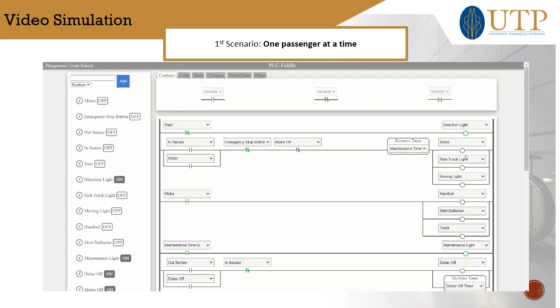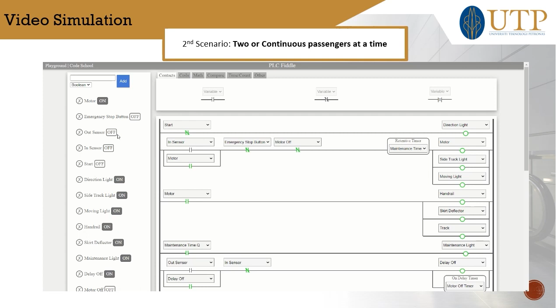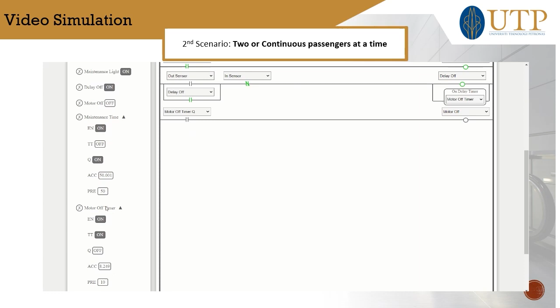Alright, so let's move to the second scenario, when there are two or continuous passengers. The in sensor is activated, the motor is on, the out sensor is on, but it's still on. And then let's say another passenger enters, you can see the motor off timer will be reset to 0. So the escalator will not stop operating, and only when the out sensor is activated, it will delay by 10 seconds. The values here, 10 seconds and 50 seconds, are shortened for the sake of simulation.